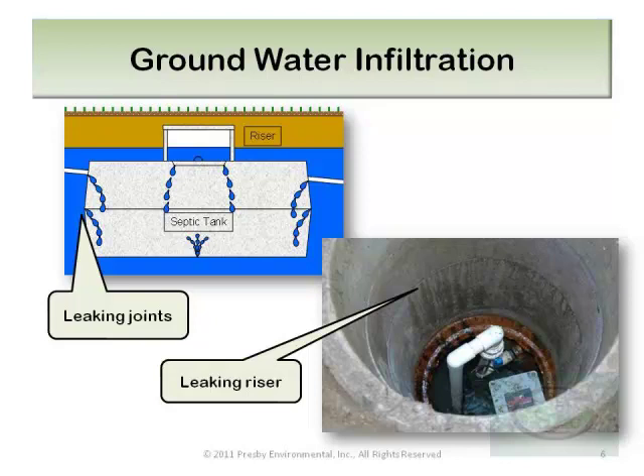If you're going to use an existing tank, have it pumped and watch for any signs of leaking. And it goes without saying, never climb into a septic tank that's been in use. There can be asphyxiating gases that will linger in a tank and can easily render you incapacitated. Leaking tanks should only be repaired from the outside or entirely replaced.